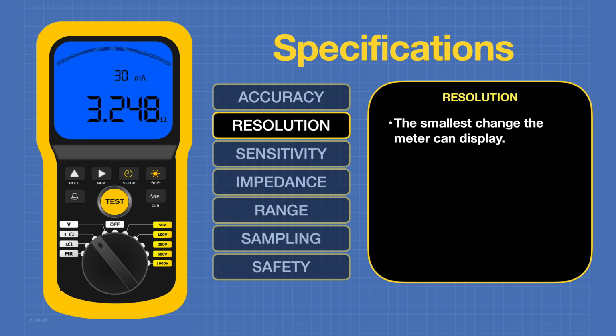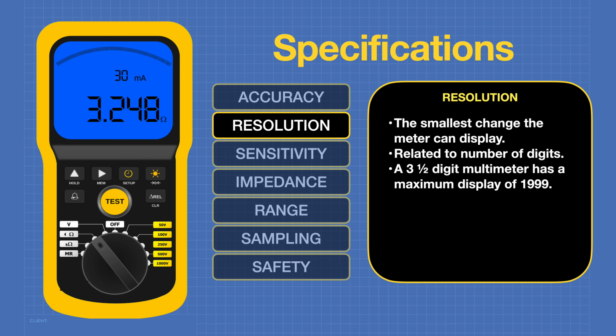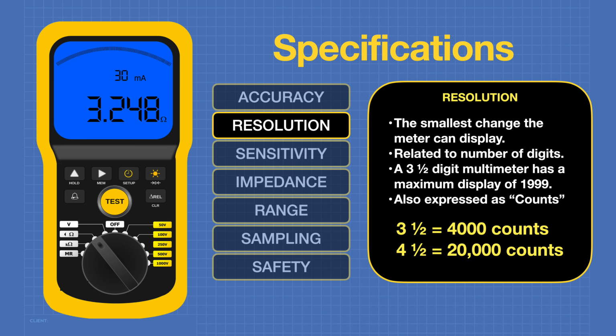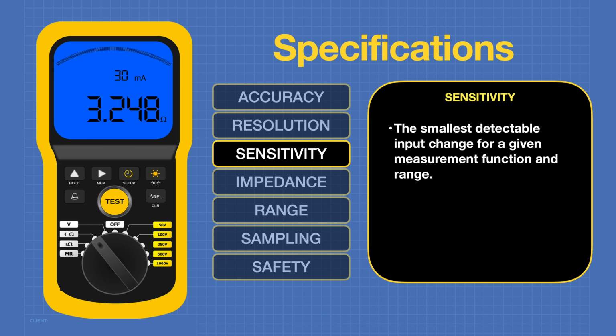Resolution is defined as the smallest change that the meter can display. This is related to the number of digits on the multimeter. A 3.5-digit multimeter has a maximum display of 1999, the 1 being considered the half digit. This can also be expressed as counts. We define sensitivity as the smallest detectable input change for a given measurement function and range, so there will be several sensitivity measurements in a multimeter spec sheet. The unit used depends upon function.